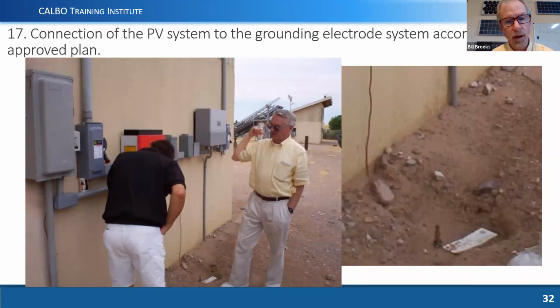It's not all that common that we would have to install a grounding electrode, but on older homes it is more common for sure. And so in a lot of communities, especially with older homes, they'll have water pipe grounding, which, if all the pipes are metallic, they're excellent grounds. But unfortunately, what happens over time is those metal pipes get replaced with plastic pipes, and then we lose our connection to earth.